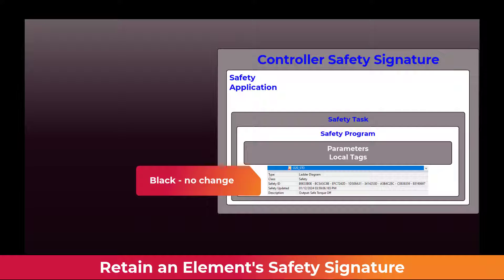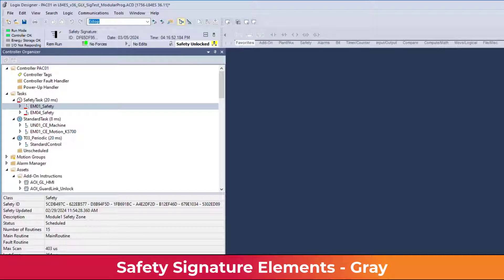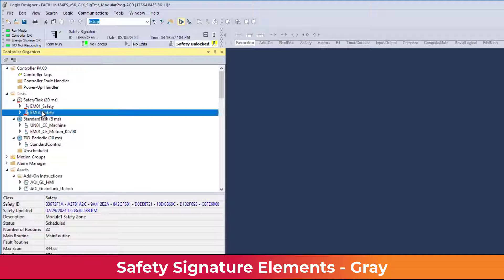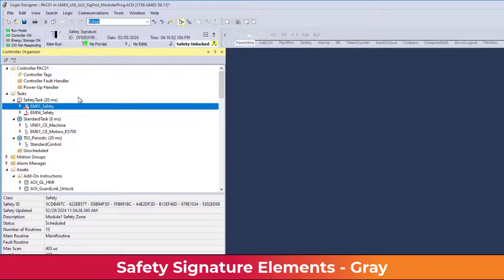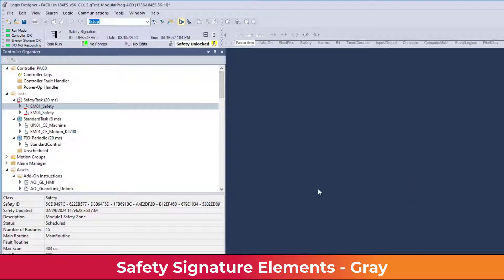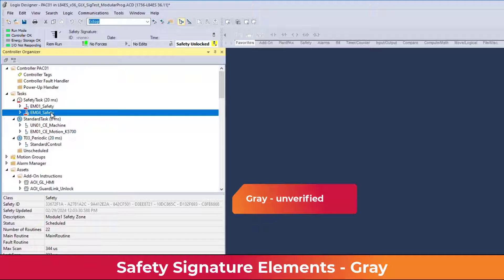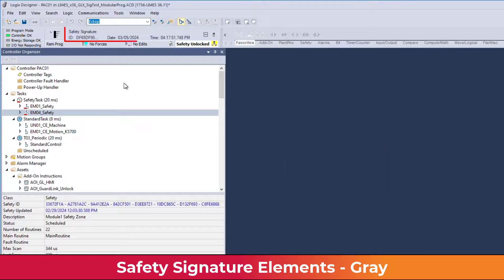The parent element, such as the program for a routine, will indicate the presence of change in blue. The color gray indicates an unverified element signature. If the controller safety signature is removed, the signature elements display as gray. Previously verified elements copied or imported into an application also display as gray. The gray transitions to black or blue when the controller safety signature is generated.